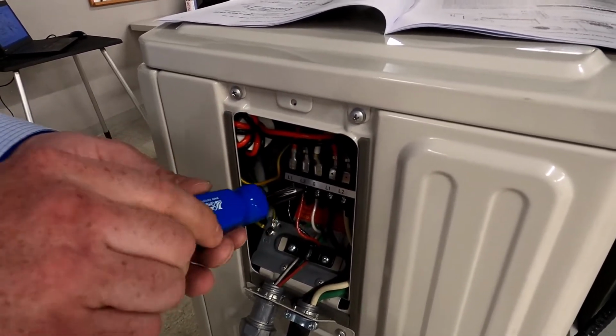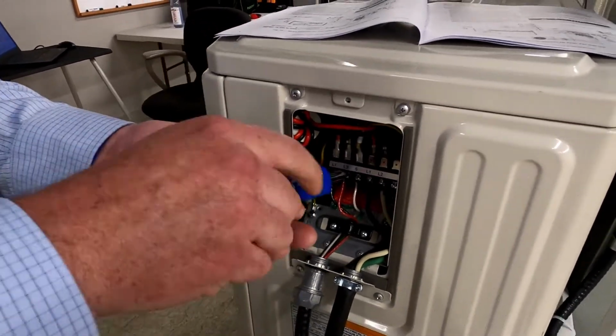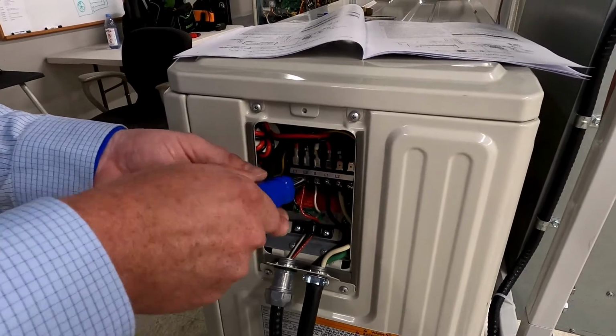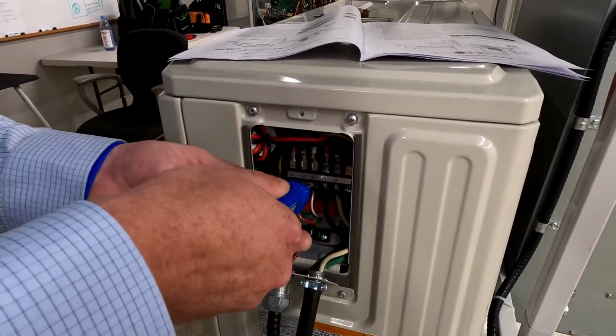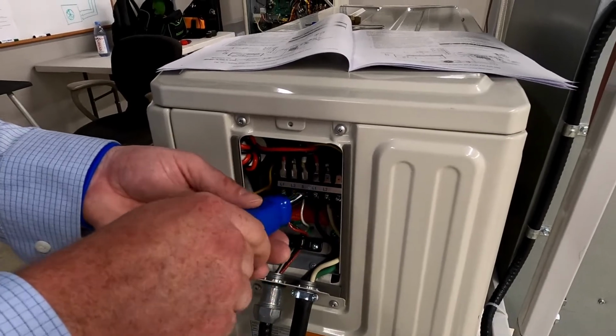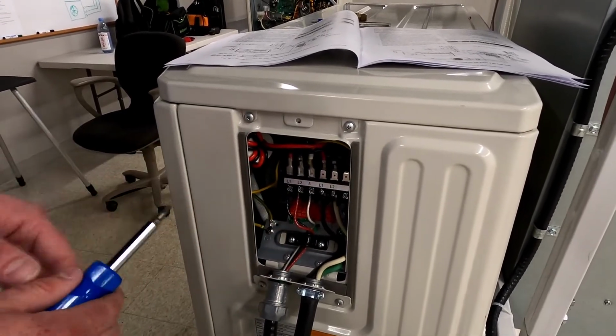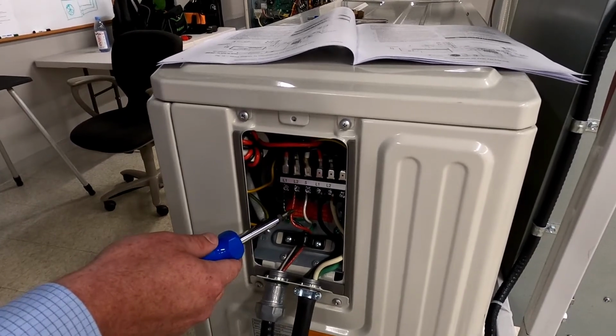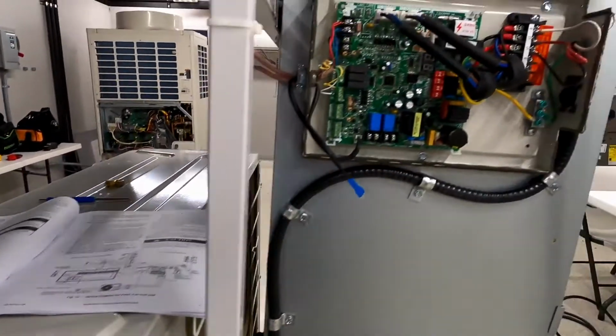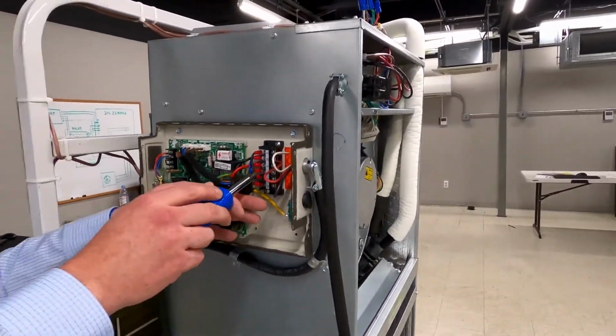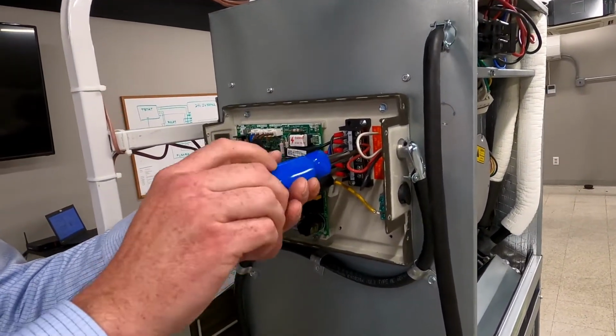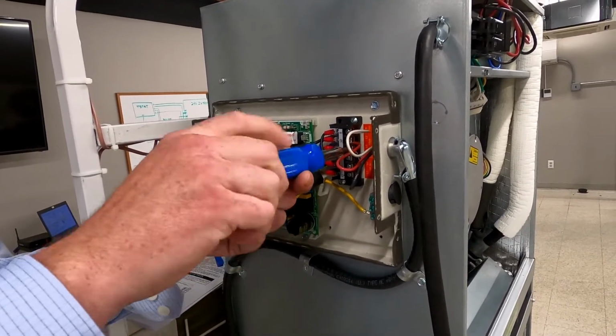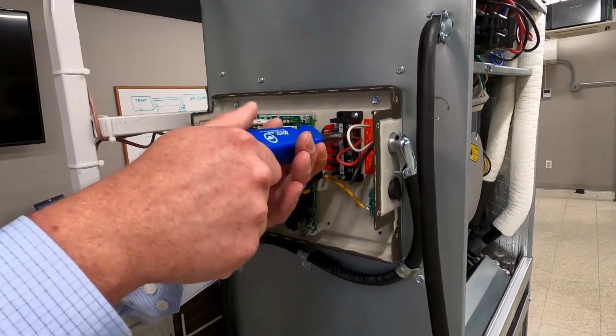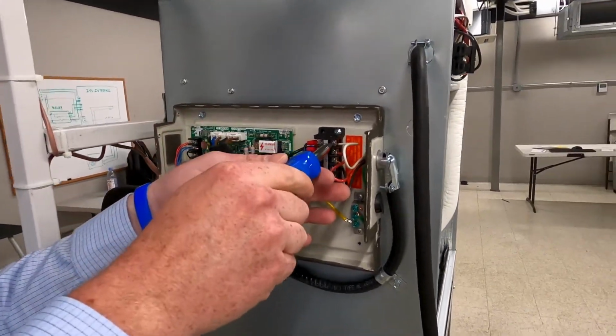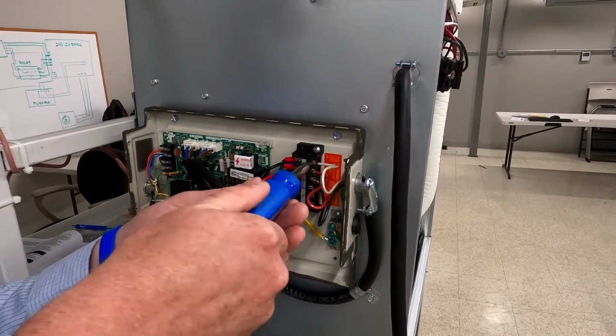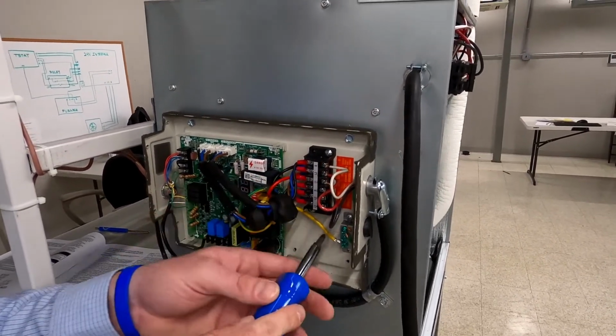When you're hooking up L1, L2, and S, make note of which color goes where. If L1 and L2 get flip-flopped, then you'll have a communication error. You also want to ensure that you don't put line voltage on either of the S terminals. So for this example, we use black for L1, red for L2, and white for S. Now we're going to go to our interface kit and tighten those connections down. Black is L1, red is L2, and white is S. And we'll also tighten down our ground.